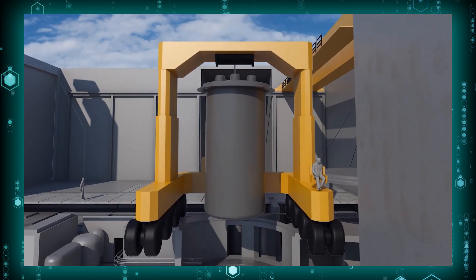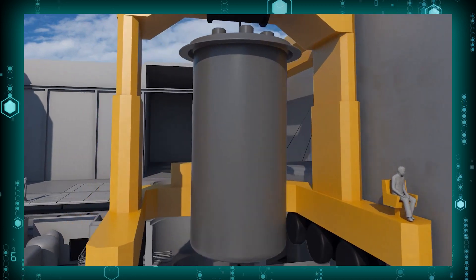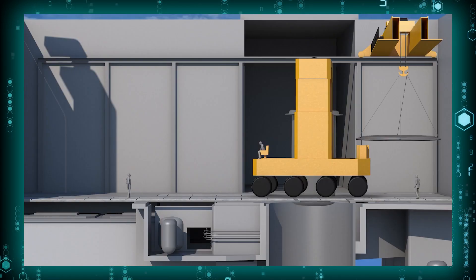It's designed to run for 7 years, after which the core is replaced and a new molten salt reactor is dropped in to continue operation. Unlike previous reactors, this design uses low-enriched uranium fuel with less than 5% uranium-235. This is a big deal because by using standard enrichment, you avoid the cost and time issues of re-licensing uranium enrichment plants, which drastically removes hurdles associated with the deployment and commercialization of the reactor.